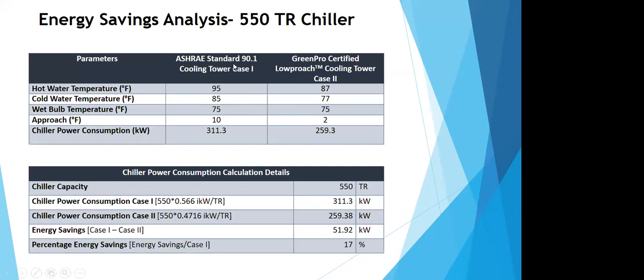The first case is based on the ISHRAE standard, the energy standard 90.1. And in the other case, we have taken the low approach cooling tower, and we have compared the performance of both these chillers. So in the case of ISHRAE standard 90.1, the design conditions laid down are 95 incoming hot water to the cooling tower, outlet is 85, and wet bulb is 75. So you can see that the approach laid down by ISHRAE chapter 90.1 is around 10 degrees.